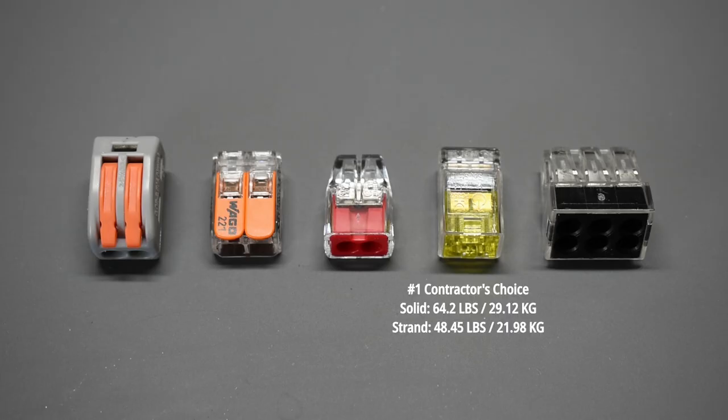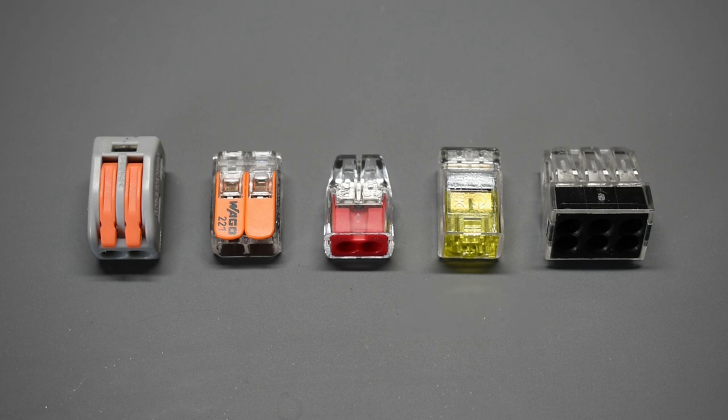For the best overall performance for solid and stranded wire we have contractor's choice. In second place we have the Wego 773 connector. Solid performing extremely well very similar to the contractor's choice. And stranded coming in just a little bit lower than contractor's choice.